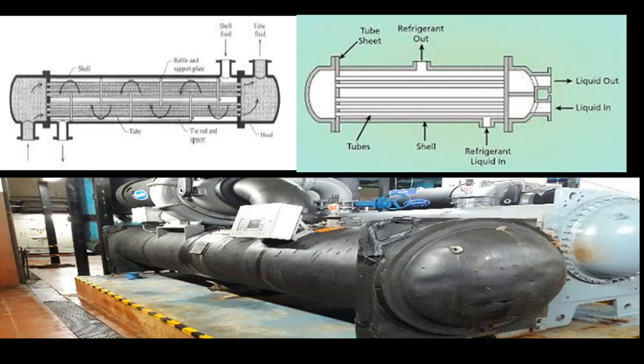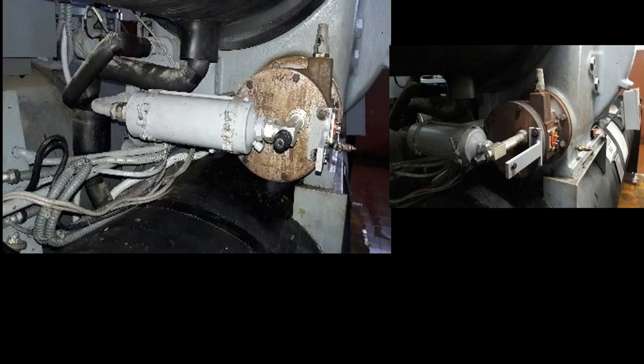The oil pump forces oil to mix into a return oil stream, which enters a heat exchanger — usually a plate or shell and tube type — where refrigerant or cooling water removes unwanted heat. To maintain a specified supply oil temperature, the oil is sent to the top of the compressor, usually passing through an oil filter before entering a small oil reservoir. The filter prevents foreign particles from entering moving components. The reservoir provides an emergency gravity-fed supply of oil if the chiller suddenly loses electrical power, sustaining lubrication until rotating components come to a complete stop.